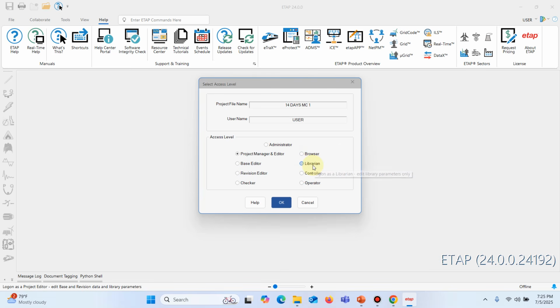Now we have the librarian. As a librarian, you can only control or edit the library parameters for various electrical equipment on ETAP software. ETAP has a vast library of equipment from different manufacturers - cables, motors, transmission lines, transformers. So your job as a librarian is only to edit those library parameters. You can even create your own library parameter on ETAP software.